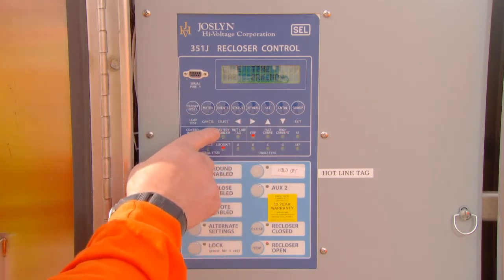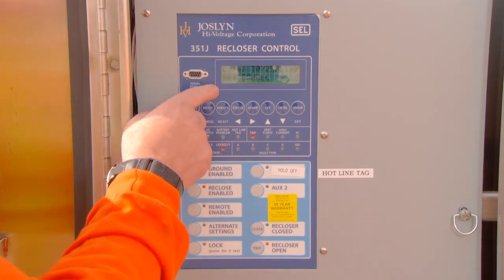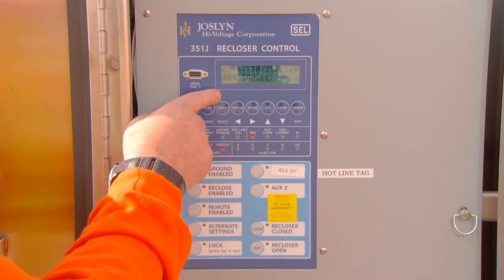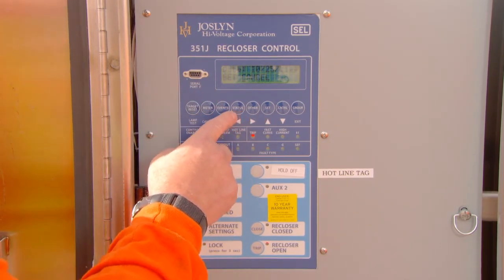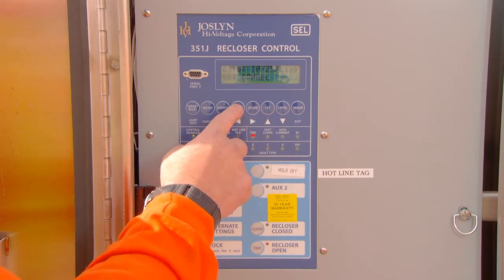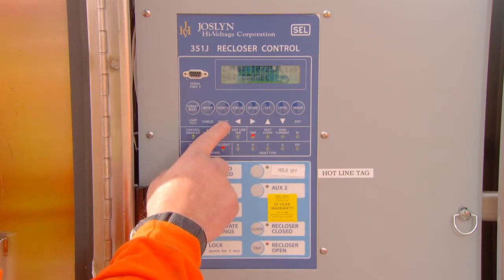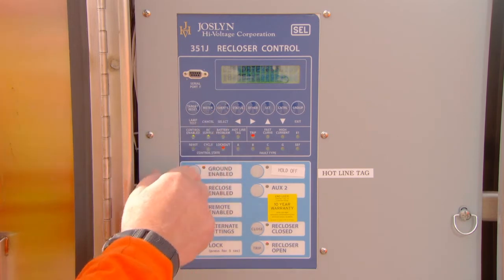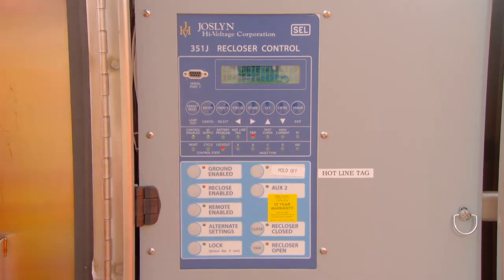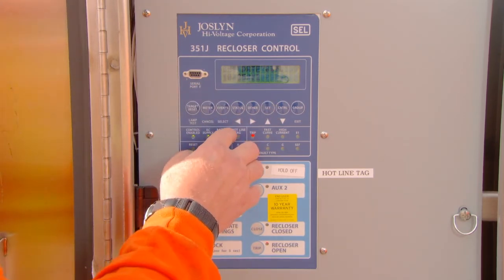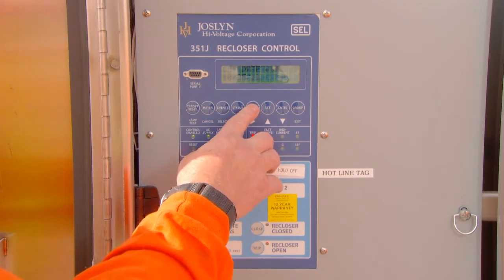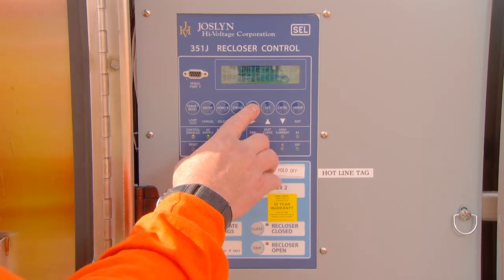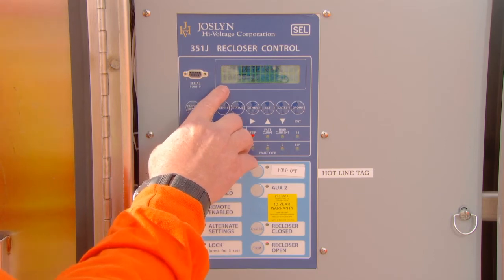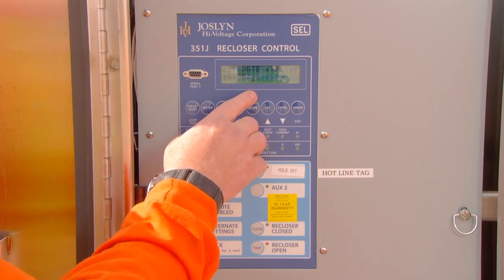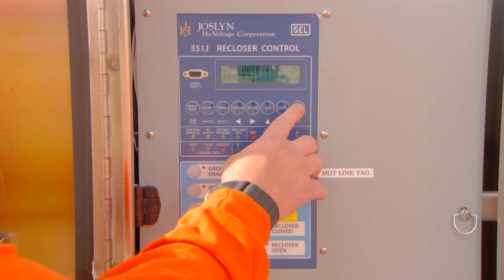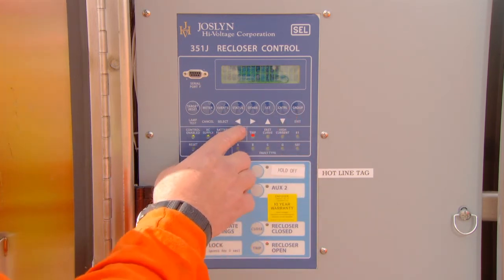The high-level function for the Other button allows you to select the date. You'll see an underscore under the date. Now, after pressing the Select button, which is the redefined Events button, you can either set or cancel a value. Using the arrow keys, move the underscore to Set, and once again press the Select button. You are now free to set your actual date using the arrow keys to select the month, day, and year.